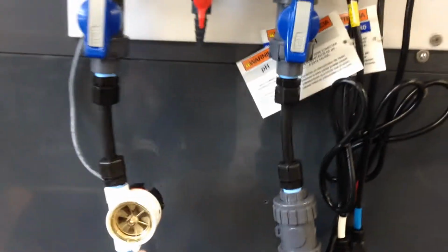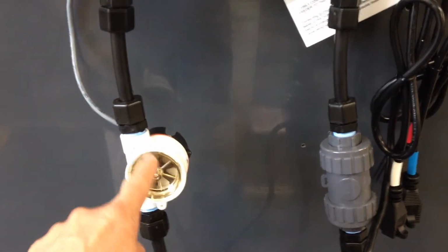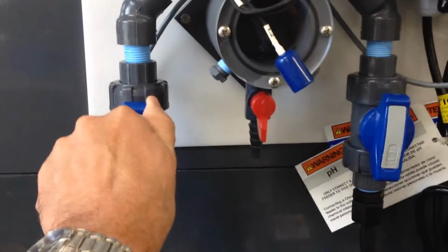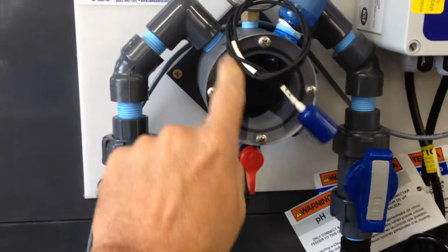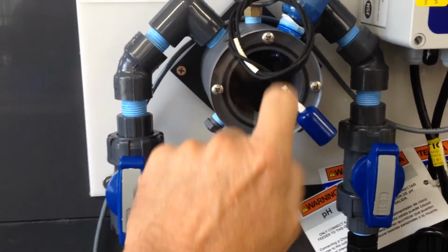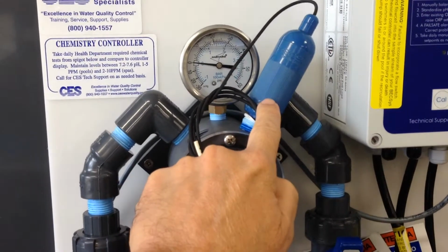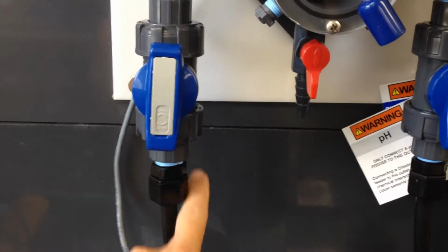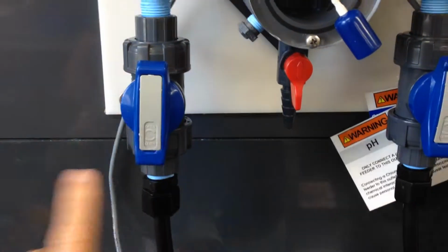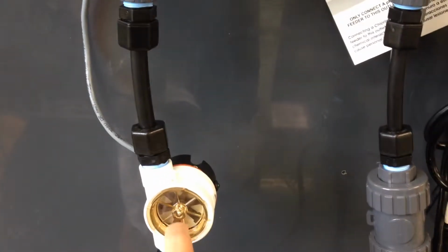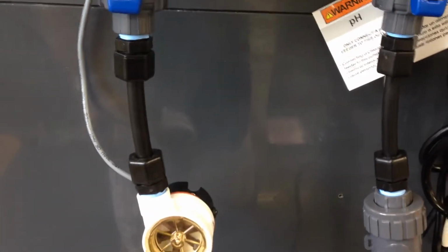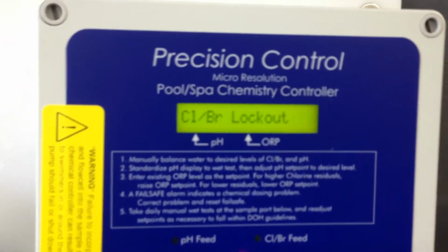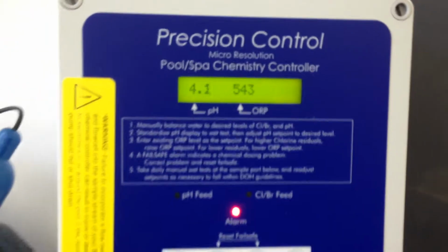You have a paddle wheel flow sensor here, which spins, and if you were to shut this valve off, there's no new water entering the probe cell, so the probes would be reading erroneously. So we have it set up that if you were to shut these two valves, or if the pump shuts off and this quits spinning, then you will get a no flow sensor, very similar to what you'll have here, chlorine lockout, and it should say no flow.